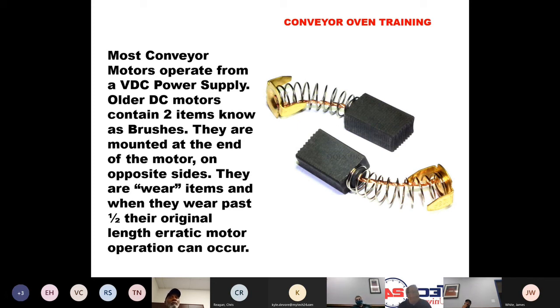Customer will say, conveyor will run for 10 minutes and then stop and then start by itself. If you have brushes in a motor, take them out. We do not want to use CO2 to blow out DC motors. We can use compressed air or we can use nitrogen. CO2 has been proven to, because it's coming out of your jug as a liquid, basically like a refrigerant, it can damage the varnish on the motor windings inside the motor. So avoid using CO2 to blow out the carbon from these.